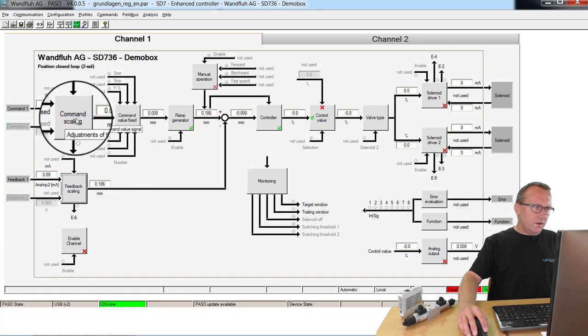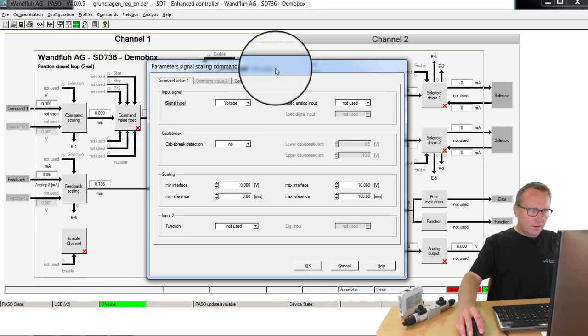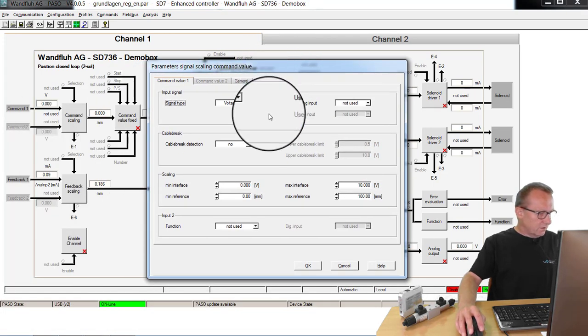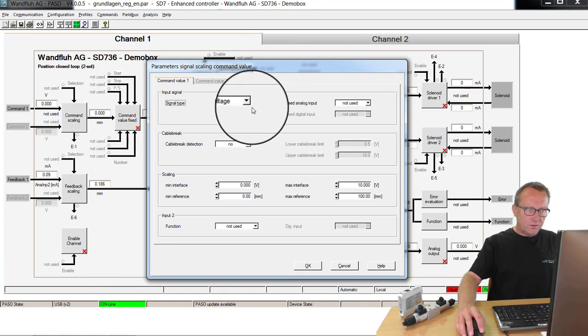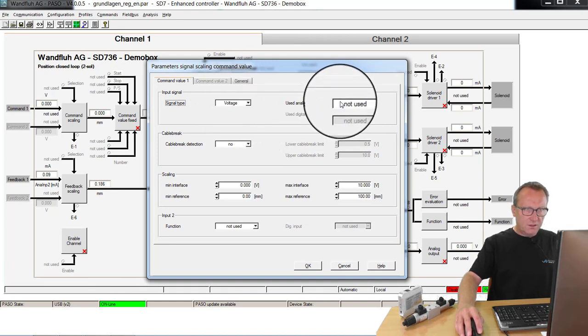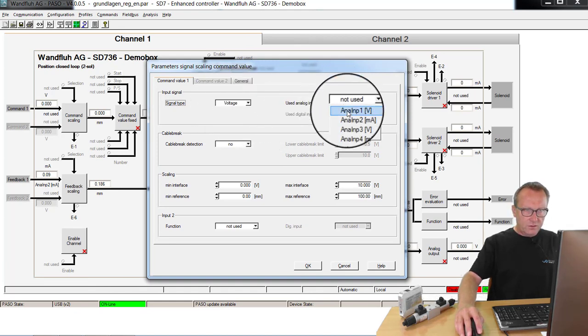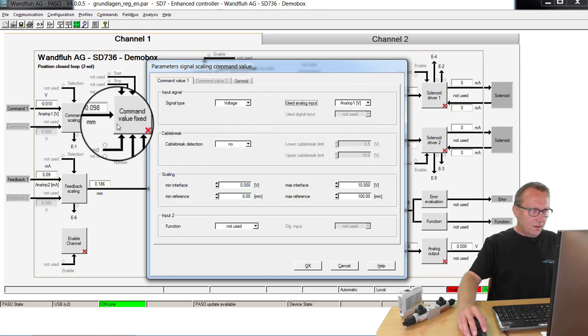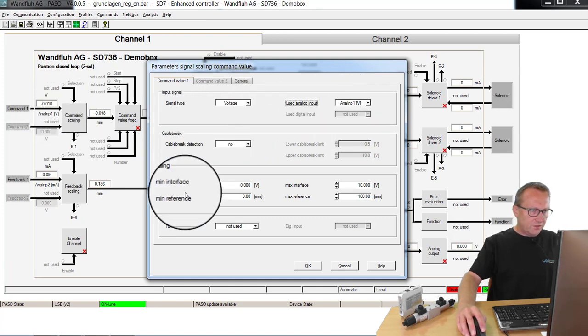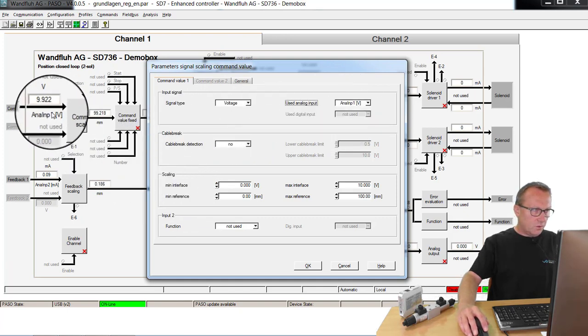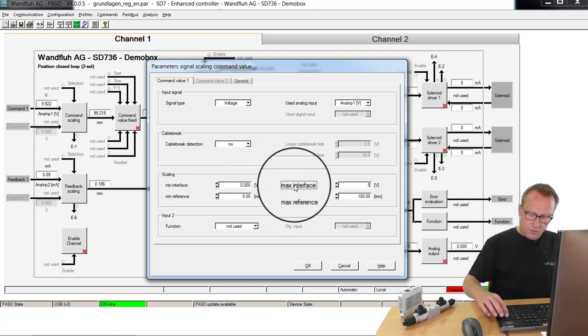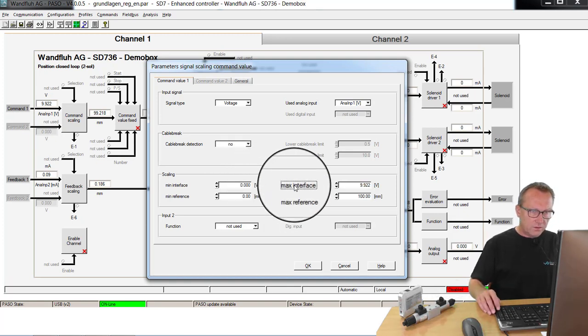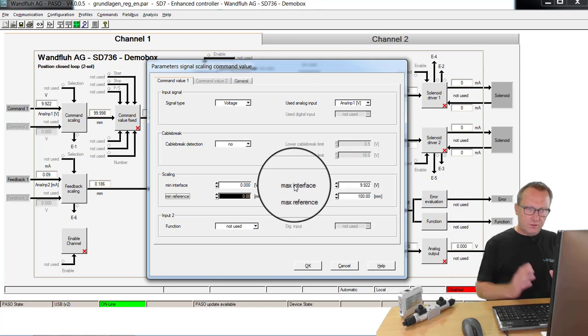I make the command scaling. On this demo application, the command value is a potentiometer voltage signal connected to analog input 1. The range is 0 up to 9.922 volts.